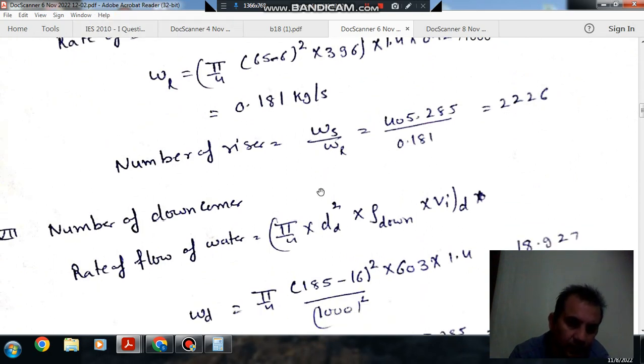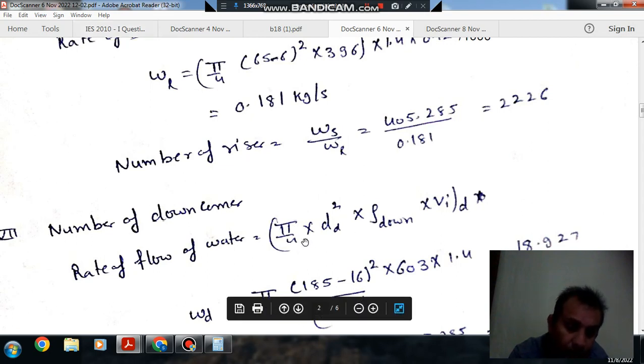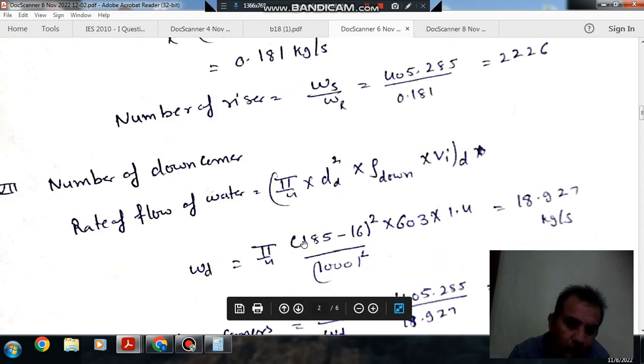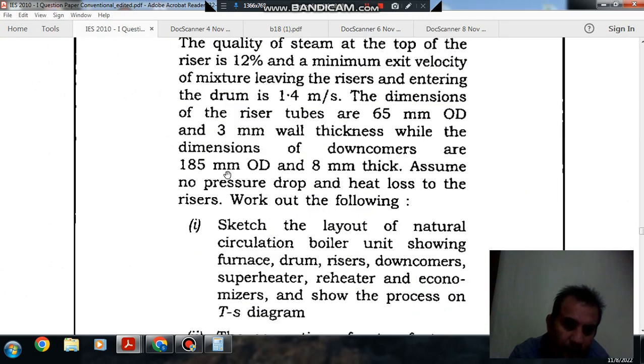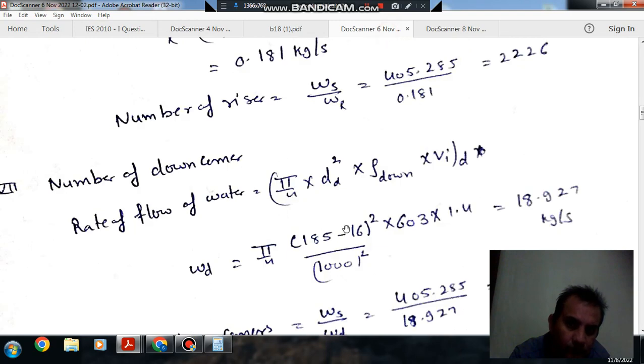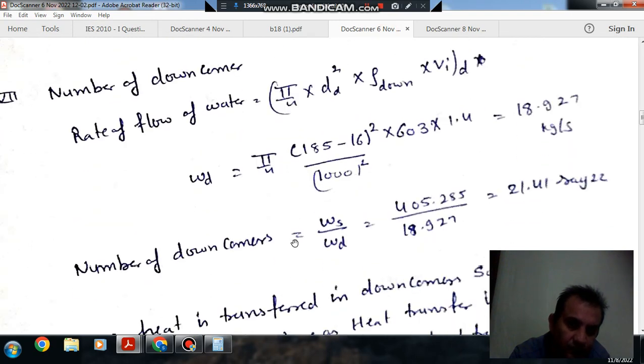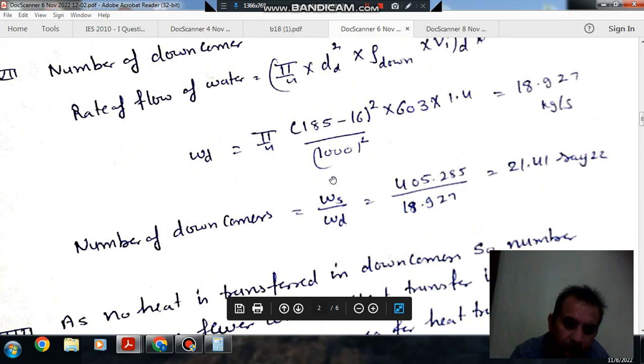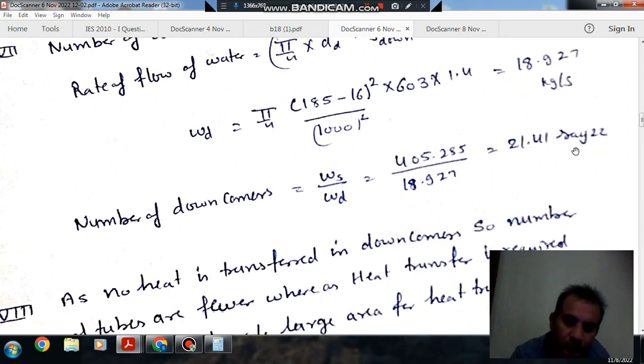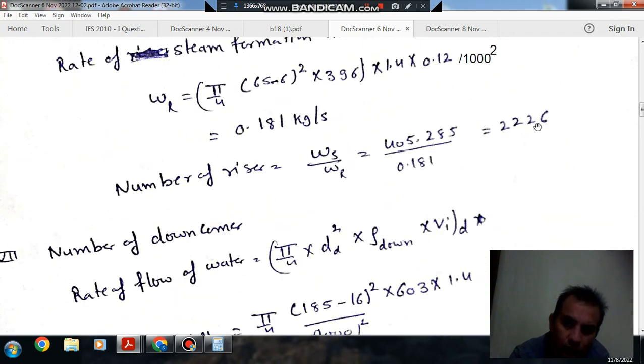So next is number of downcomers. Again by following the same procedure, as in downcomers the water is flowing, the mass flow rate in one downcomer is calculated. And outer diameter of the downcomer is given as 185 mm and thickness is given as 8, so inner diameter will come out as 169 mm. So number of downcomers comes out as 22.